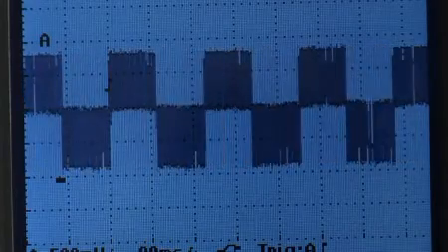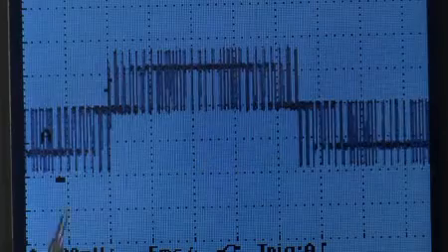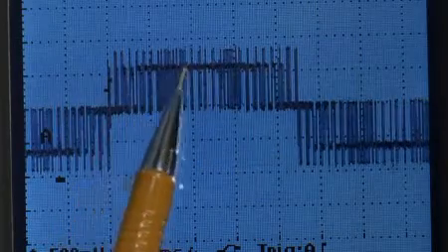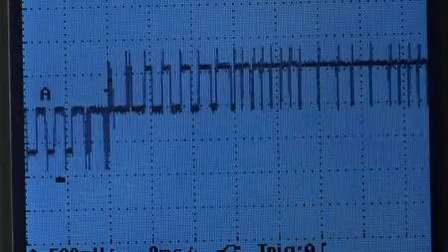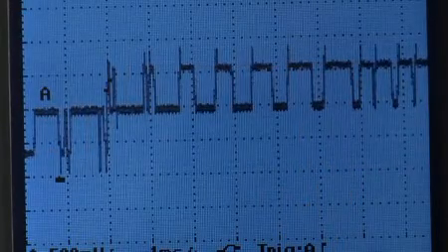Thanks to the Fluke Scope Meter's wide bandwidth and fast sampling, it's easy to capture the peak voltage caused by the cable reflections. We can even zoom in and get a better picture of the magnitude of the transients.